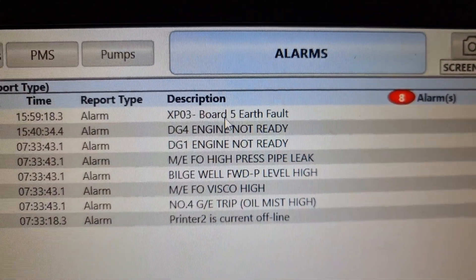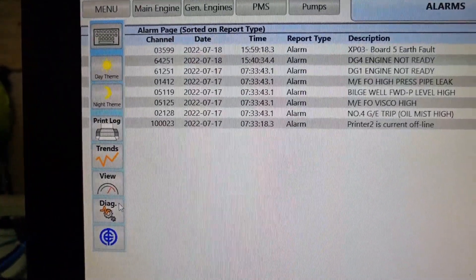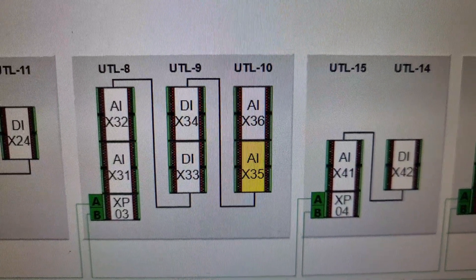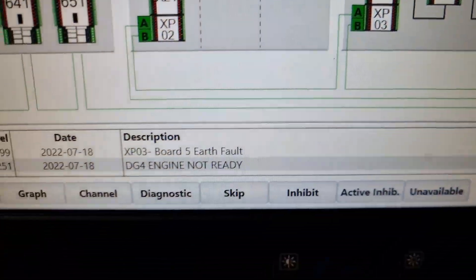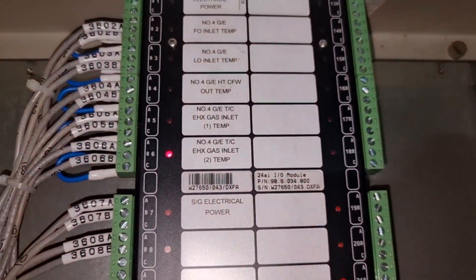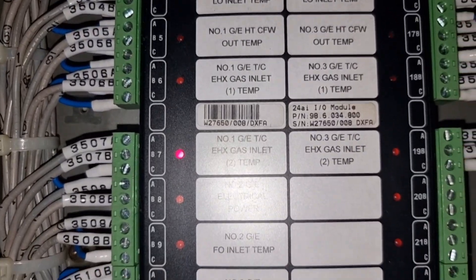This is to avoid a blackout or even a shutdown of the main engine. We have an earth fault on our alarm and monitoring system — a 24-volt earth fault. Fortunately, this Terasaki system has earth fault monitoring. A color yellow on our analog input X35 in the UTL 10 cabinet means we have an earth fault. I went to the UTL 10 cabinet, which is near generator number three, and opening this cabinet you will find all the alarms and systems connected to this analog input card. Checking these alarms, it will not affect our system or cause any shutdown on our generators.